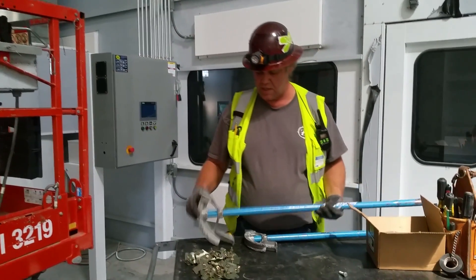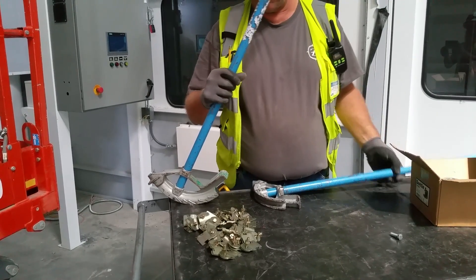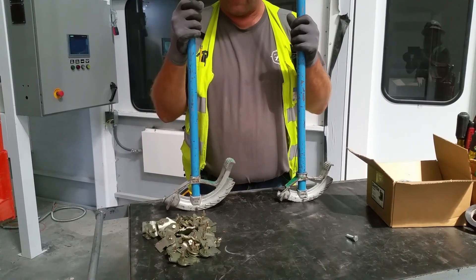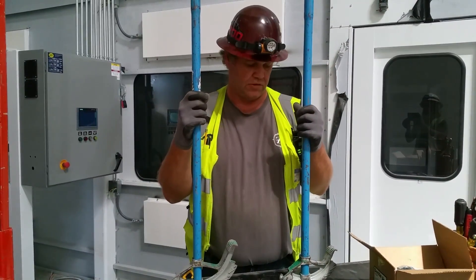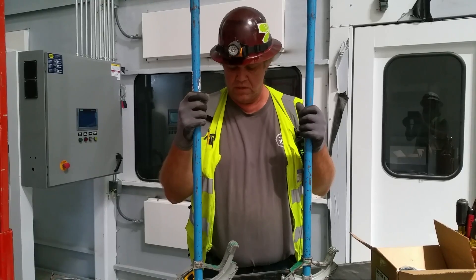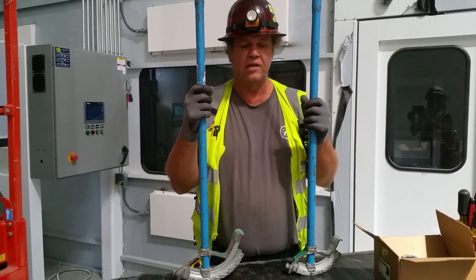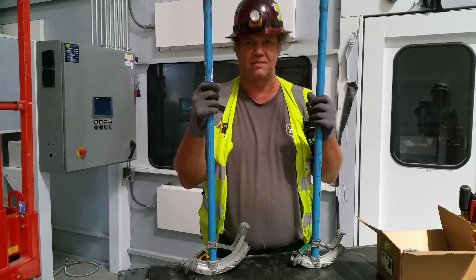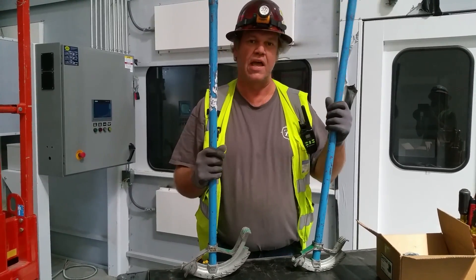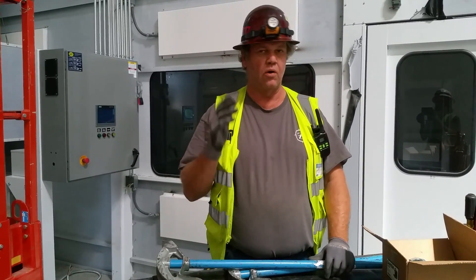My bender of choice is an Ideal. The difference between the Ideal and the Rigid benders is only one major thing: when the handle is straight up on a Rigid, it's 30 degrees; when the handle is straight up on an Ideal, it's 45 degrees. 30 degrees is the bend of choice for electricians because the math is easy — that's the sole reason. You can do the math in your head for your hypotenuse length.